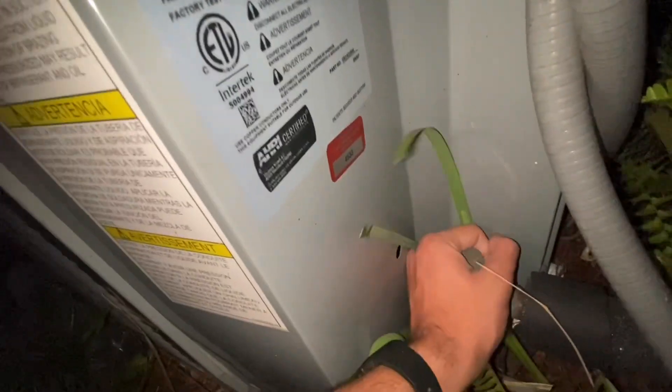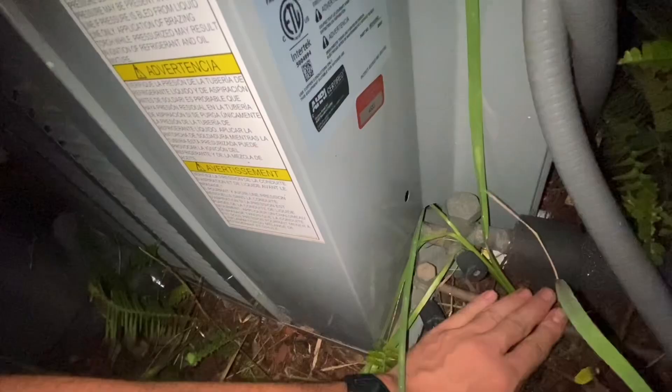This one here is not running — I don't even think it was. That is a DX 13, 5-ton from 2018, three-phase. The pipe is cold but it's not sweaty. I'm not sure which one of these was added, because there used to be one refrigerator component right here and it got replaced with these two units — so one of them was added and one got replaced with the refrigerator component.